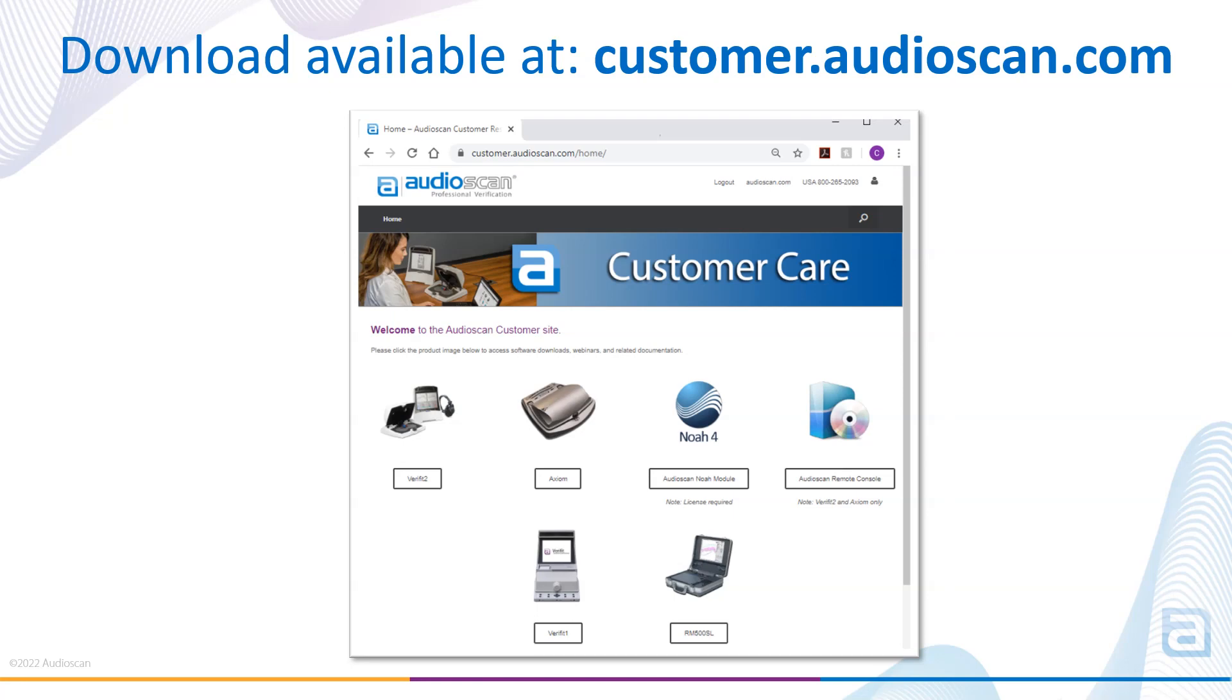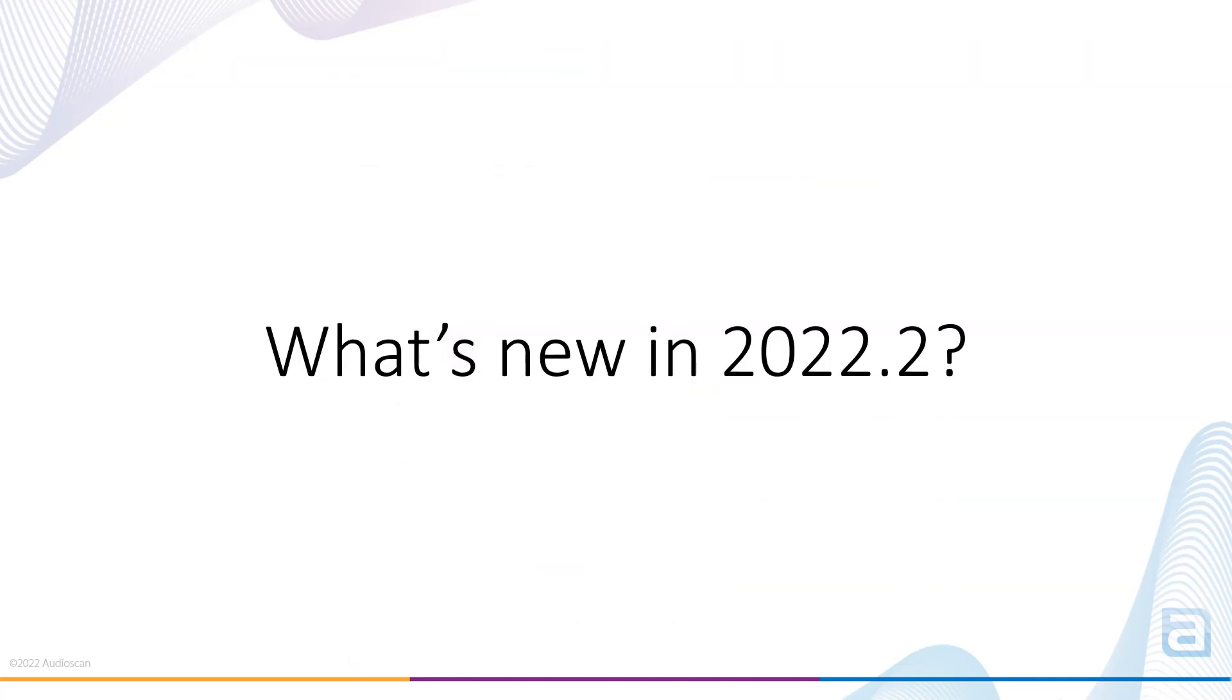Following this update for the equipment and Audioscan Noah module software, updates can be done directly from the Audioscan Noah module if your PC is connected to the internet. However, for this update, you're going to need to minimally update the Audioscan Noah module via the customer download site.